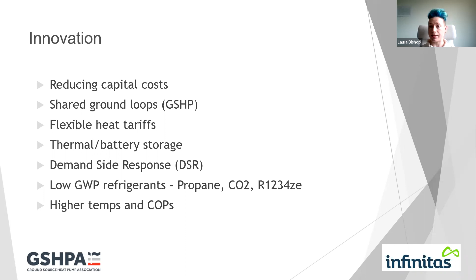There's still a lot of innovation going on with high temperatures and higher COPs, staged heat pumps. Ammonia heat pumps have been around for a very long time, 90 to 95 degrees C, but the COP does suffer. But we are starting to see, with the use of new refrigerants, higher temperatures being possible with higher COPs.